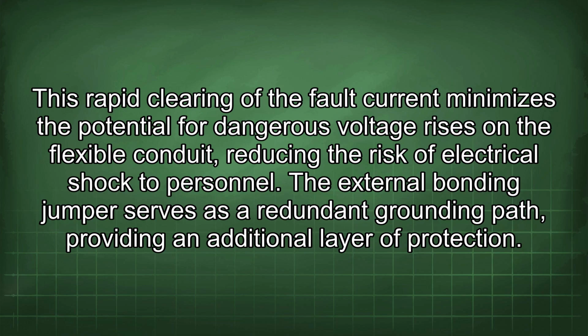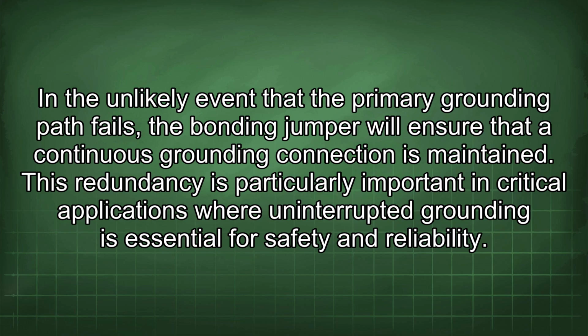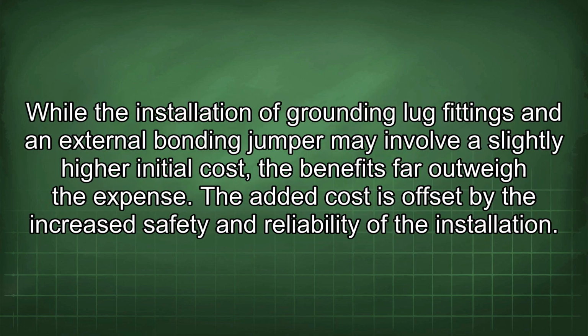The external bonding jumper serves as a redundant grounding path, providing an additional layer of protection. In the unlikely event that the primary grounding path fails, the bonding jumper will ensure that a continuous grounding connection is maintained. This redundancy is particularly important in critical applications where uninterrupted grounding is essential for safety and reliability. While the installation of grounding lug fittings and an external bonding jumper may involve a slightly higher initial cost, the benefits far outweigh the expense. The added cost is offset by the increased safety and reliability of the installation.